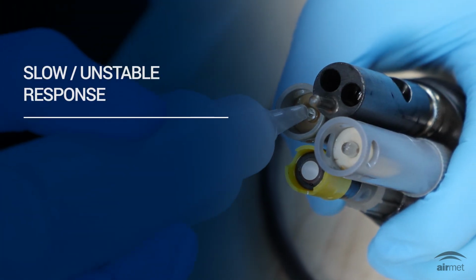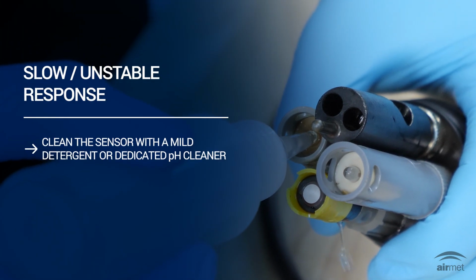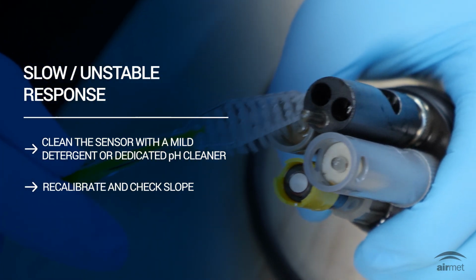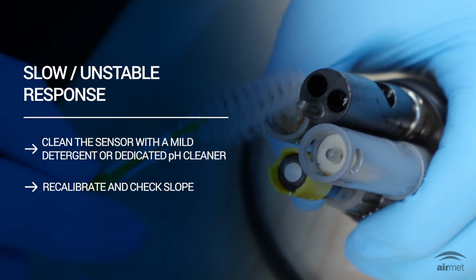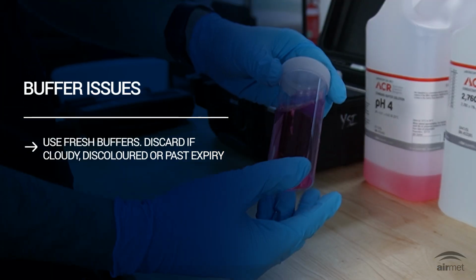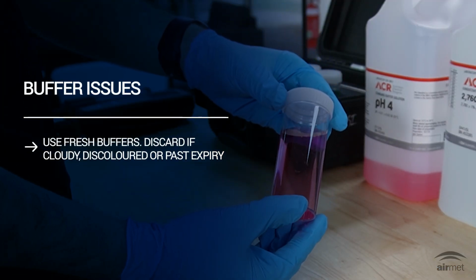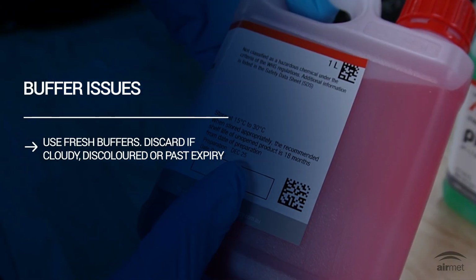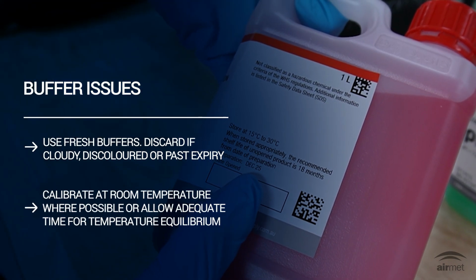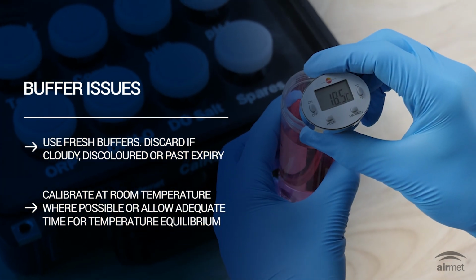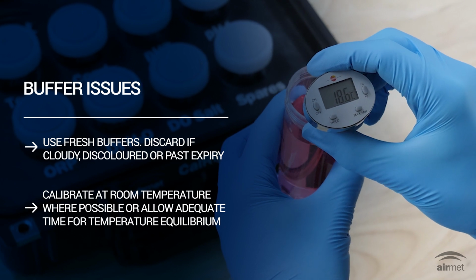Slow or unstable response. Clean the sensor with a mild detergent or pH cleaner. Recalibrate and check the slope. Buffer issues. Use fresh buffers and discard if the solution is cloudy, discolored, or past expiry. Calibrate at room temperature whenever possible to allow adequate time for temperature equilibrium.